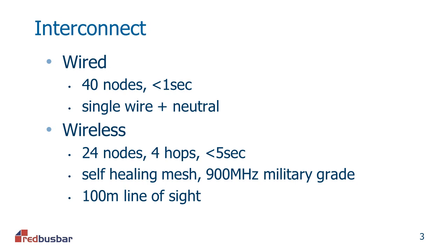Okay, let's have a look at the interconnection function. A wired interconnection is capable of connecting up to 40 nodes, and the transit time across the network of an alarm signal is less than 1 second. From a hardware perspective, a single wire, typically 1.5 square mil, is used, and the return signal is via the neutral circuit. Wireless interconnection, up to 24 nodes can be connected to the system, and the system supports up to 4 hops. So in a situation where alarm A communicates to alarm B, but alarm A can't see alarm C, then the message will be routed from A to B and B to C. So that constitutes 1 hop.